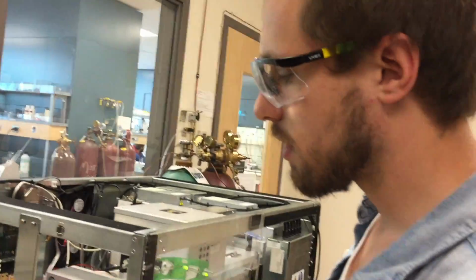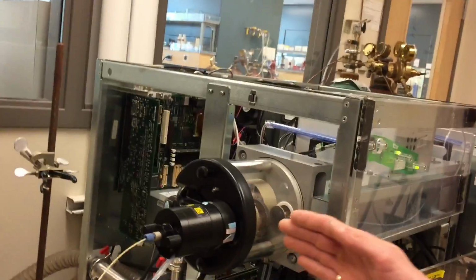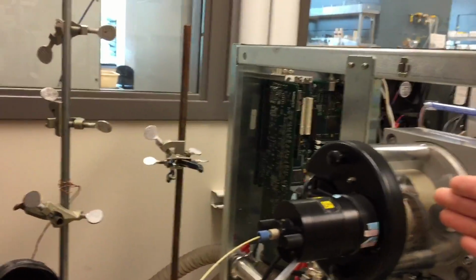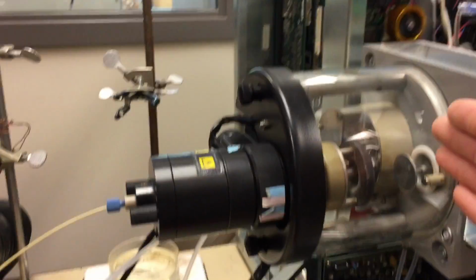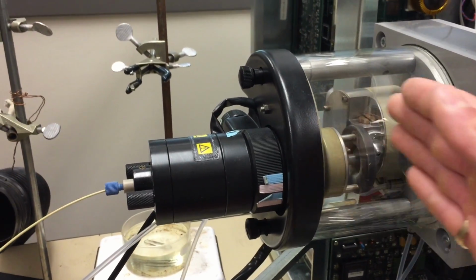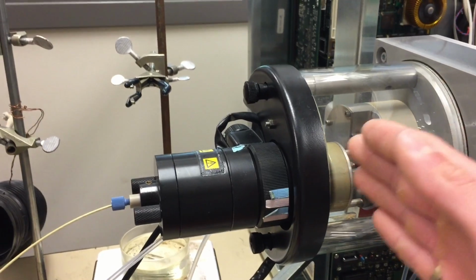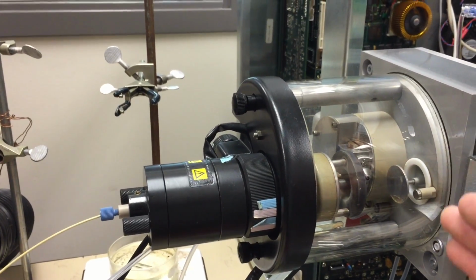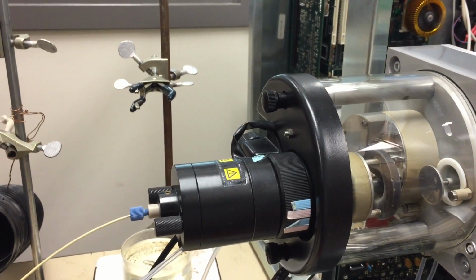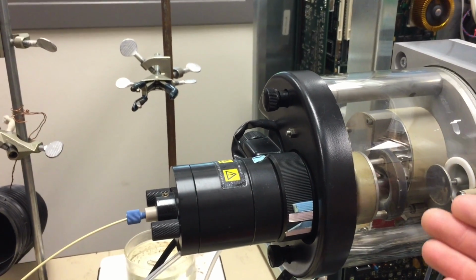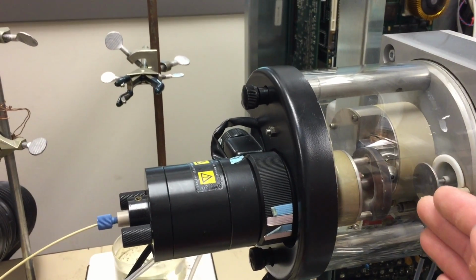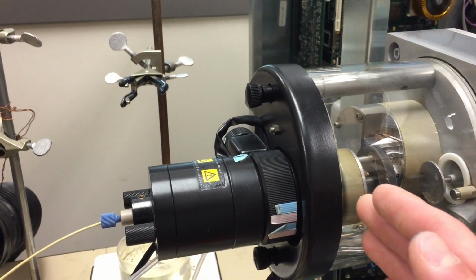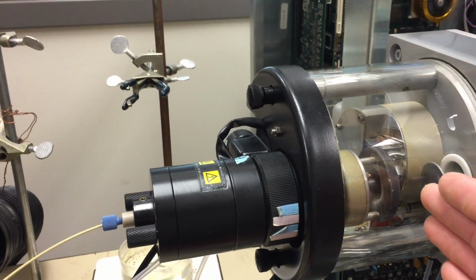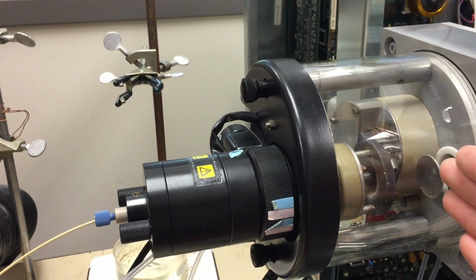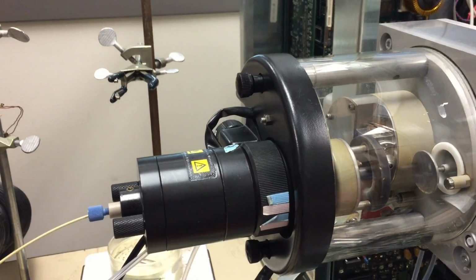Another parameter to adjust can be this XY tuning source for the head, for the source, as it allows the cone to be moved in and out and closer or farther from where it's drawn into the instrument. And larger aggregates actually fly better when the source is slightly farther away, and then the smaller aggregates are more dominant when it's closer to the inlet.